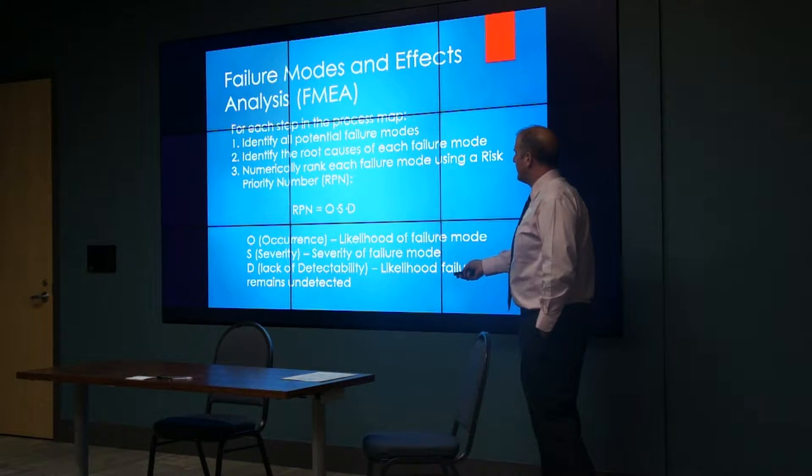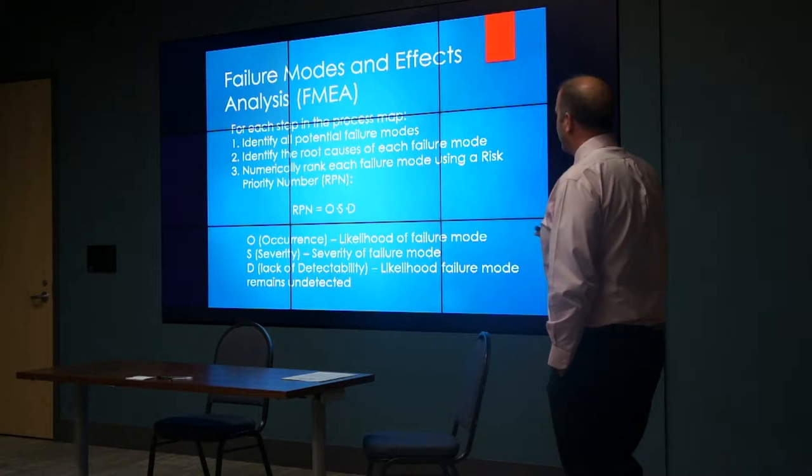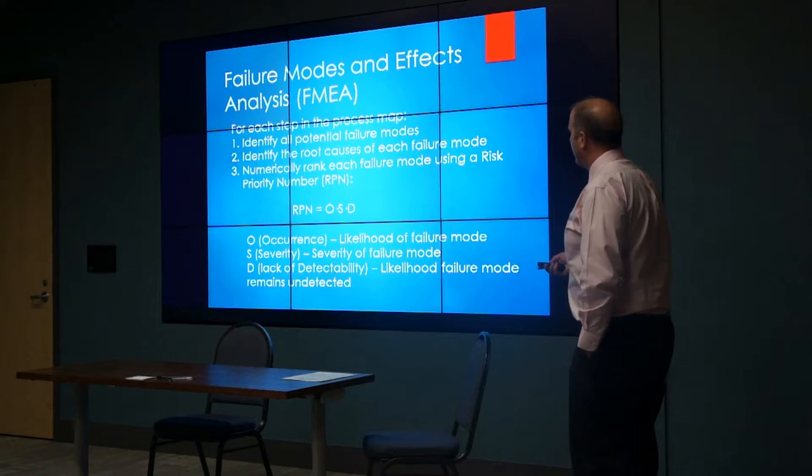The risk is proportional to the product of all three of these numbers. These numbers are given a scale from 1 to 10, so the maximum RPN would be 1,000 and the minimum would be 1. Typically, numbers less than 100 are usually ignored—risks not significant enough to pay attention to. The ones higher than that are the ones you really need to address in your quality management program to make sure you prevent those risks.